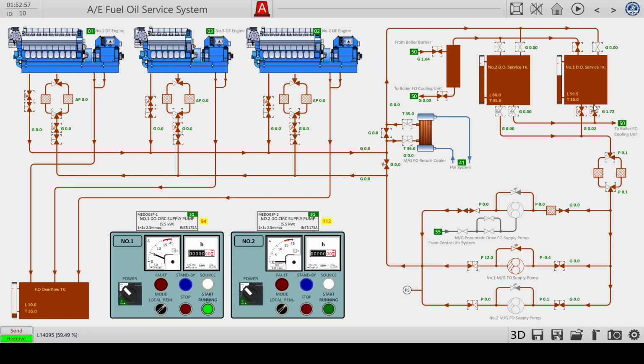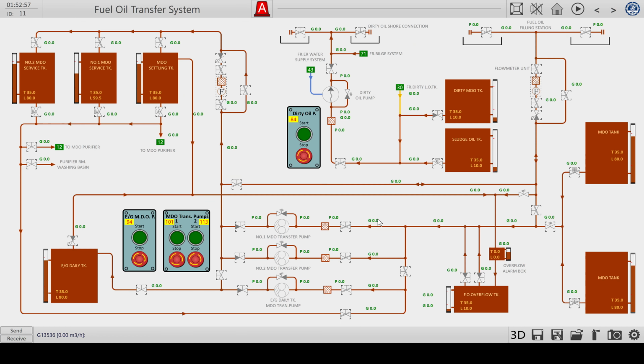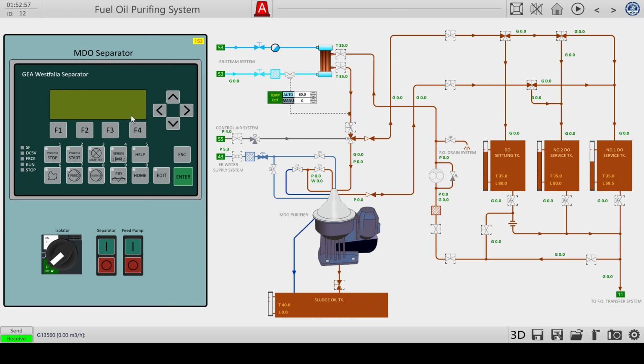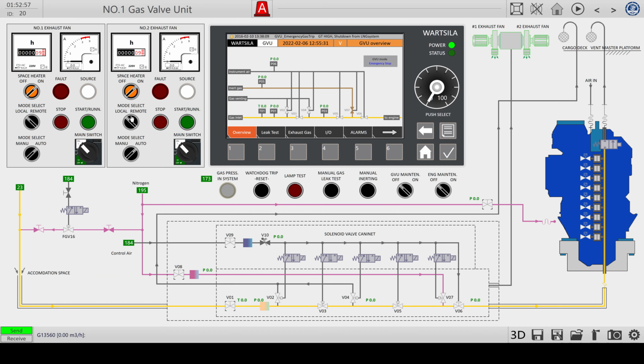We're using diesel oil from the first service tank in the diesel generators via the first supply pump. The first service tank is at around 60%, so we're fine by that. Purification isn't needed at the moment.